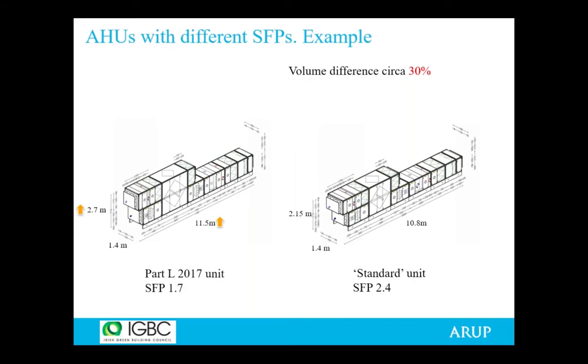The implication, as you see in the image on the left, is that the fan needs to be larger, and the coil and air handling unit need to be larger. This shows an example for an operating theatre - I wouldn't say the old system was inefficient, but let's say the old system's minimum requirements, against the new air handling unit with an SFP fan efficiency parameter of 1.7, show a volume difference of around 30%. So if you multiply this by 100 air handling units for a hospital, there could be quite a difference in terms of space requirement.